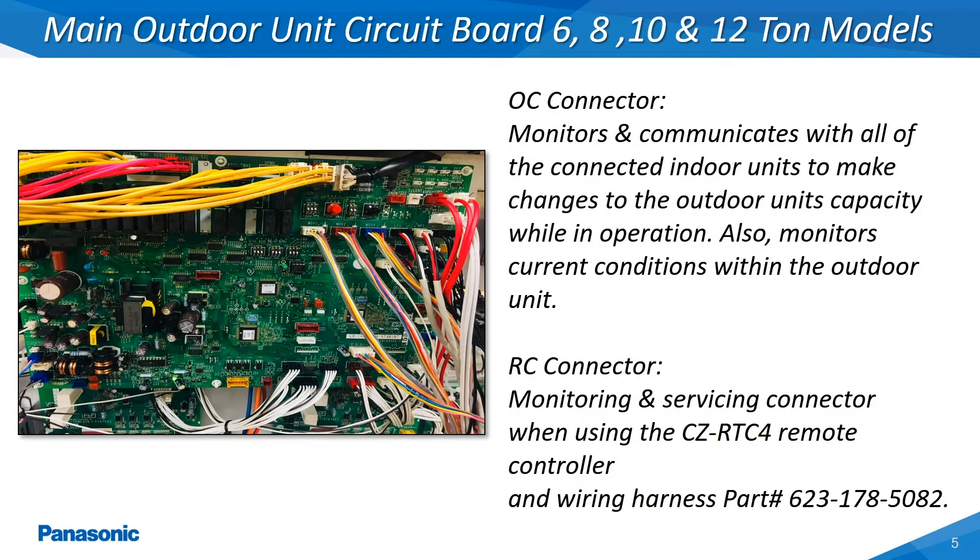The ECOi outdoor unit's main printed circuit board is the primary board which also receives continual packets of information back from all of the connected indoor units. This board will also monitor the current operation within the outdoor unit and make any necessary changes in order to maintain optimal performance. These outdoor units, when doubled and tripled together, will also be communicating back and forth, broadcasting command signals along with the current data being monitored between all of the connected outdoor units. Many of these details can be seen by plugging the servicing remote controller with the associated wiring harness into the RC connector located on this board.